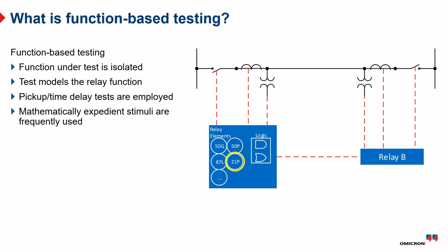In order to measure the relay's response, I have to create a model of that particular relay. So if I'm testing, say, an overcurrent element within my testing software, I have to tell the software, okay, this is SEL U3 curve, the pickup is 6 amps, and the time dial is 2.5. From this information, the testing software will then construct a model for how this relay should behave based on different test stimulus. Then I select my test stimulus, run my test, measure the relay's response, and compare the relay's response to the model that I created to make sure that the relay passed.